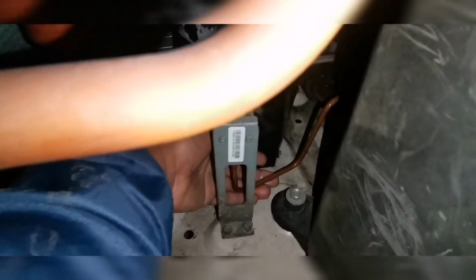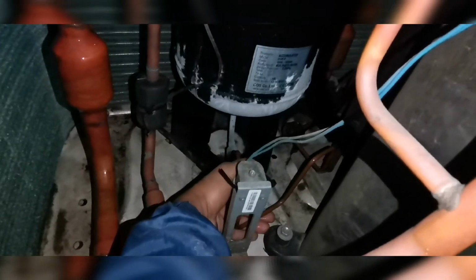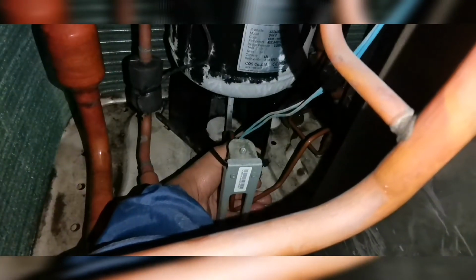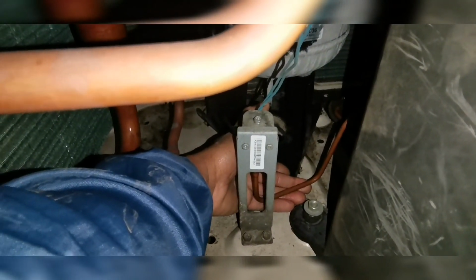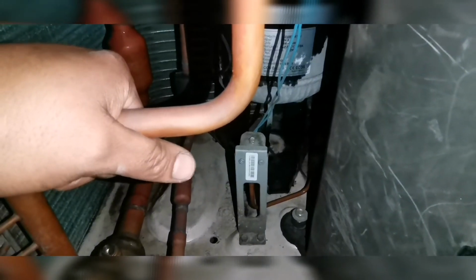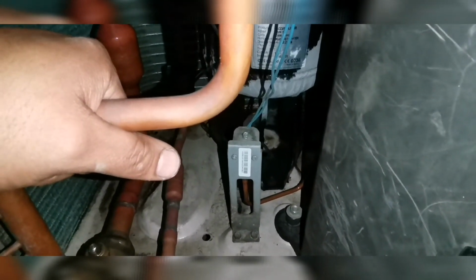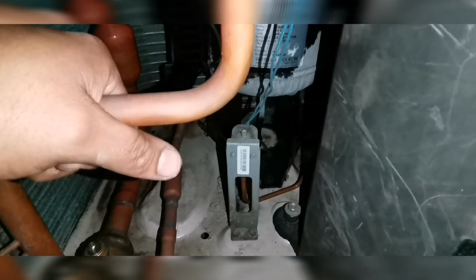So the way of doing that would be, what the manufacturer recommends is, while the system is running, because when it runs in a cooling mode, that valve is permanently open. So right now we're going to disconnect it, and what they recommend is you give it some time, and you should feel a temperature difference across. You give it about 5 minutes or so, and then you'll plug it back in and then feel the temperature difference across the two pipes again. Like I said, we do have clamps, so we'll do that so that we can actually get an accurate measurement on the temperature difference across the accumulator return valve.